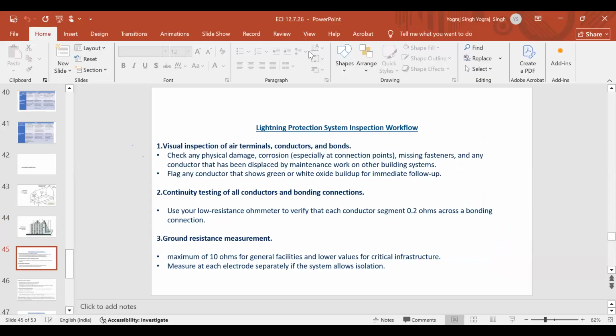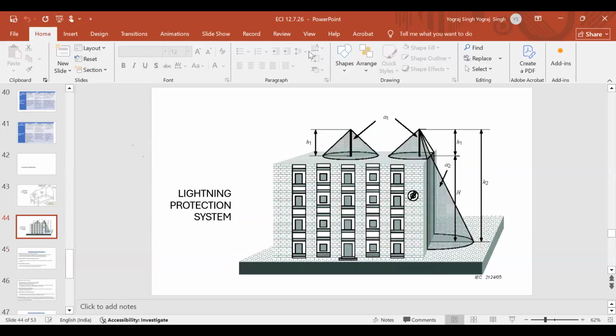Then these vertical things are finials. Finials is the highest point. Here it is sharp, so charge density will increase over here. So lightning will be attracted here. Through this conductor system, it will go into the earth. The dotted line is the floor level of the building, and this is below floor level, and it is going to earth.